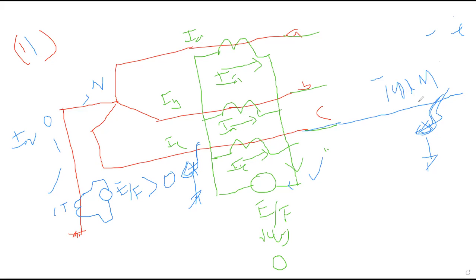Yes, sir. So that is the problem of unrestricted earth fault protection. A very far away earth fault can also trip some very essential component like a power transformer or generator, which may hamper the continuation of the power flow. So what should be our ideal case? The ideal case should be that we provide earth fault protection, but it should be limited within a range, with a boundary. Understood?